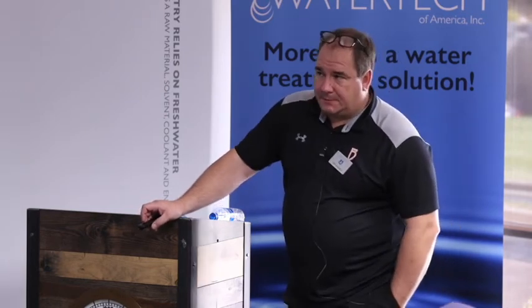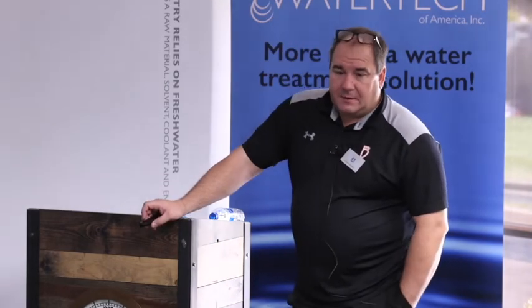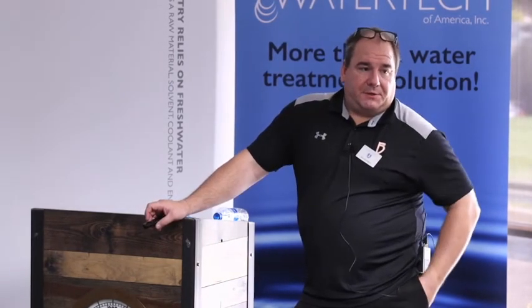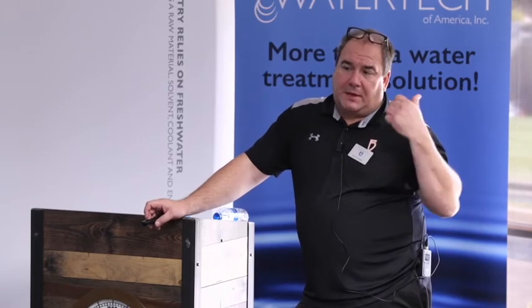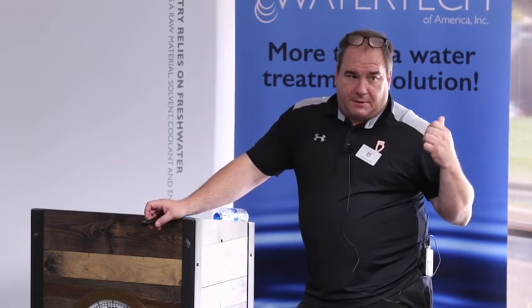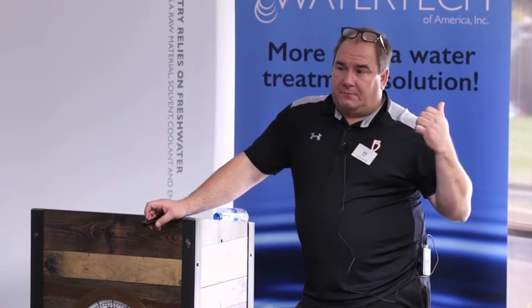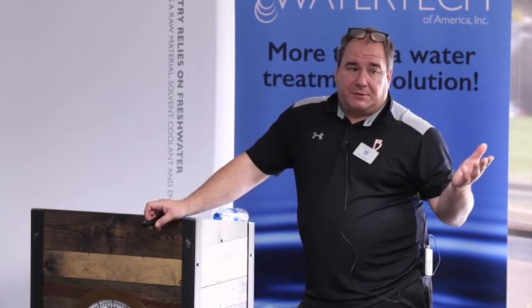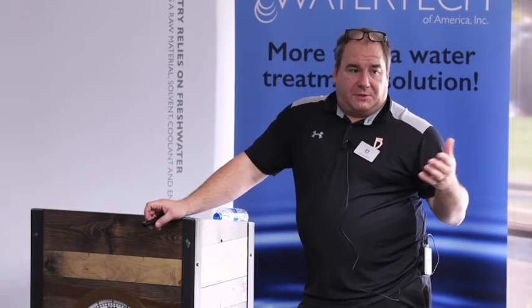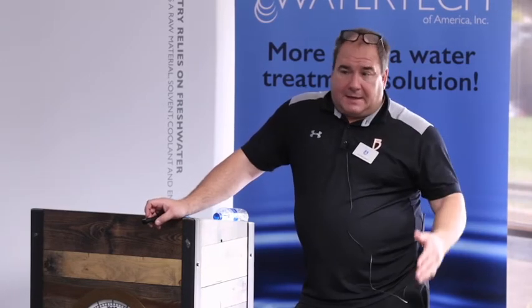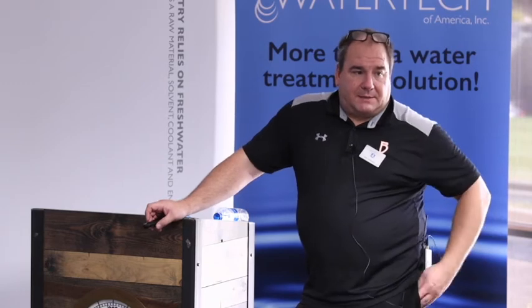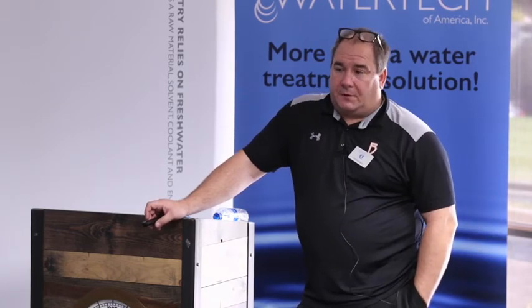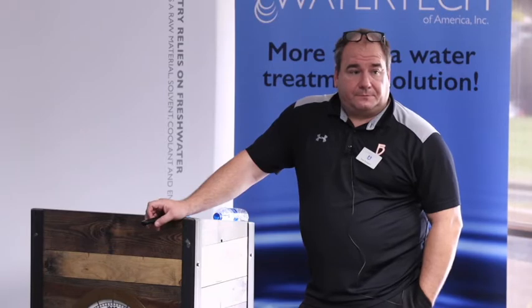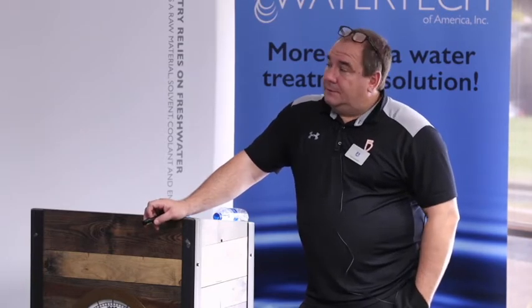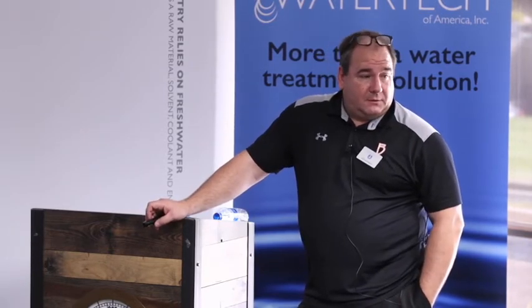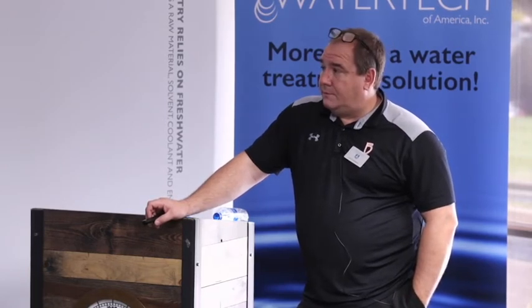We have a customer that makes some stuff, and he can tell when an operator doesn't follow the right procedure, because the plant isn't softened. The only softeners are in the boiler, and he gets hardness that comes back from his condensate system, and his conductivity shoots up to 400, which he normally doesn't see. Because he's monitoring to see what's going on, he can troubleshoot it and start looking into the reasons of what's going on. So, any other questions?